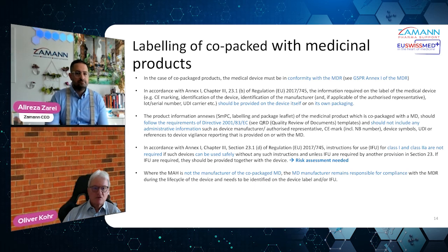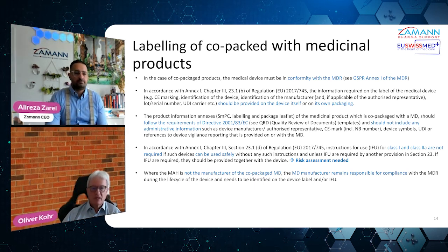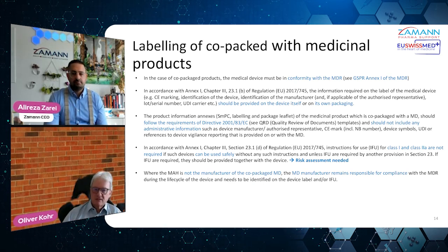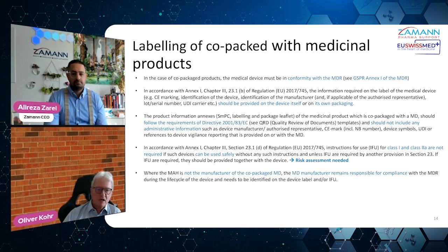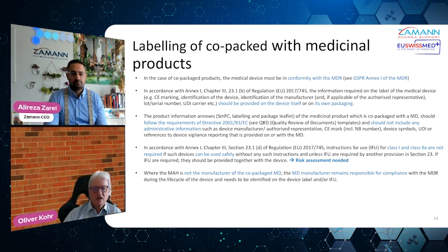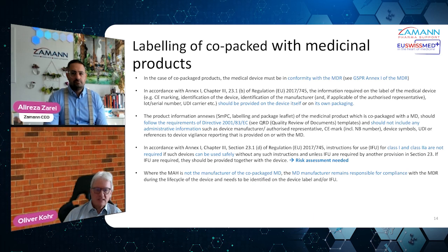Important: declaration of conformity for co-packed medical devices. It is the responsibility of the applicant, that means you as the marketing authorization holder, to ensure that the medical device it is co-packed with meets the GSPR, which is Annex 1 of the MDR, and is in compliance with the entire MDR. So that's a key thing.